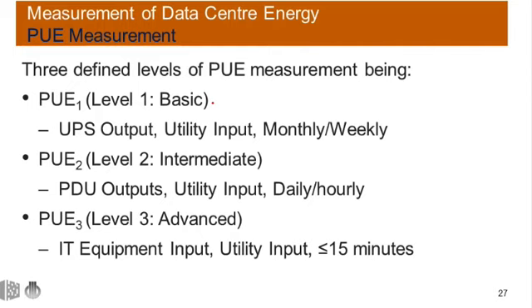So moving on to the next slide, we look at how PUE is measured within the data center. And there are 3 defined levels of PUE measurement, being a basic, intermediate and advanced level. These respective levels consider the IT energy measurement point, the total facility energy measurement point, and the measurement interval or frequency of measurement. You can see PUE1 being the level 1 basic measurement, considers UPS output, measurement at utility input, and on a monthly or weekly frequency.